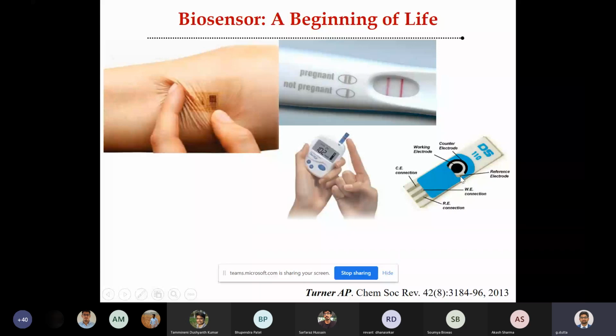So the three electrode system combined together, and it forms a sensor chip. So this working electrode, what is the working electrode? In the working area, actually we are immobilizing many bioreagents. So if you have glucose in the sample, then it will come to this working area. It will react with a reagent called glucose oxidase, which will be on the sensor surface. So glucose will react with the glucose oxidase, and during that reaction, we can generate some electrons.